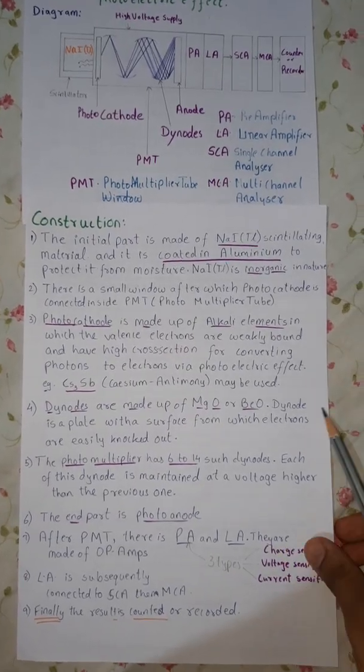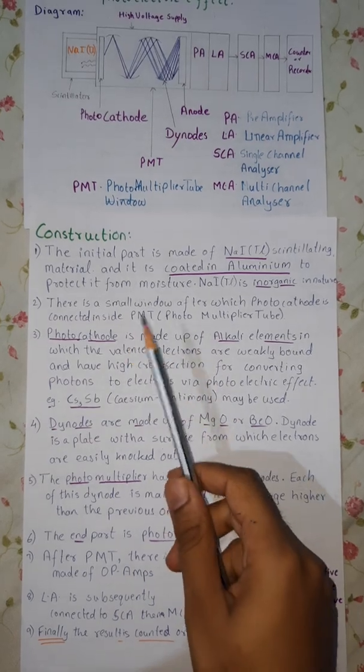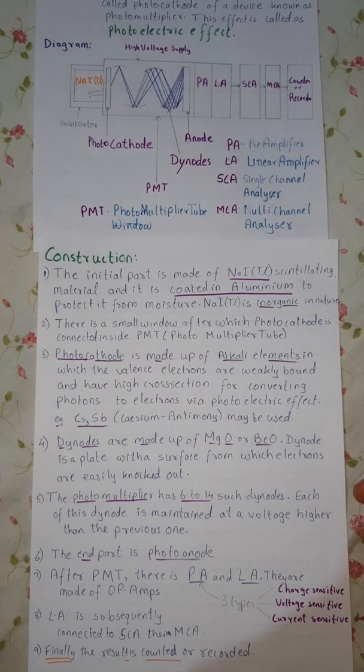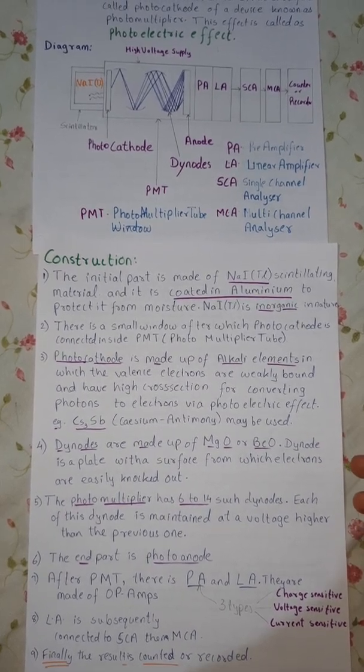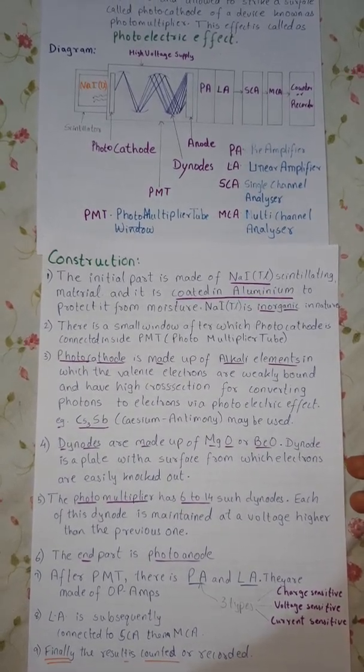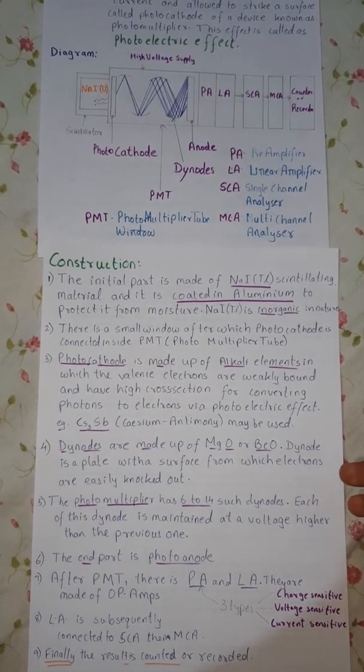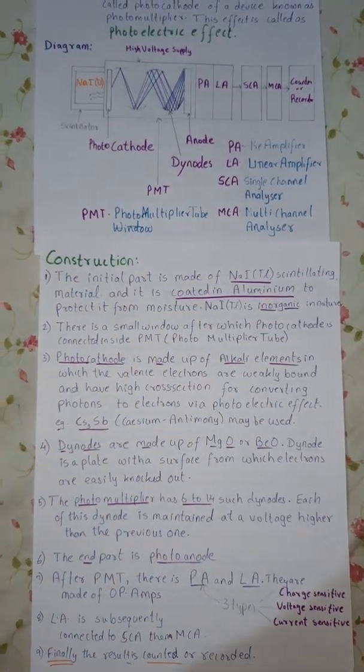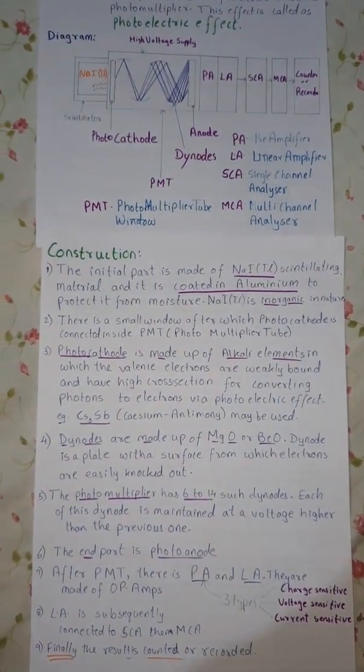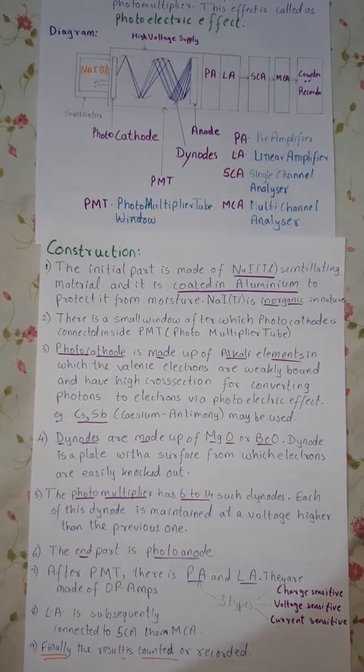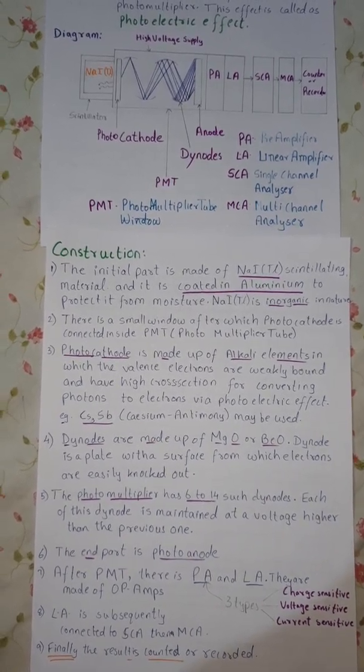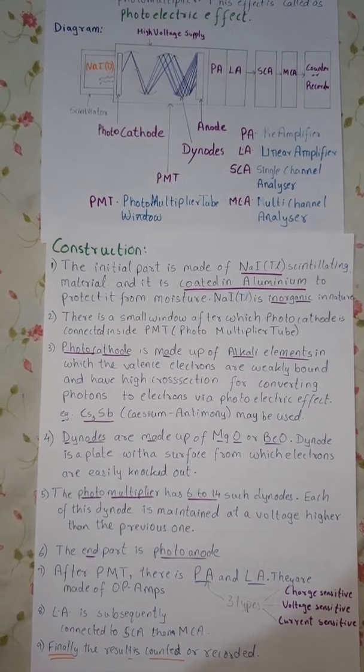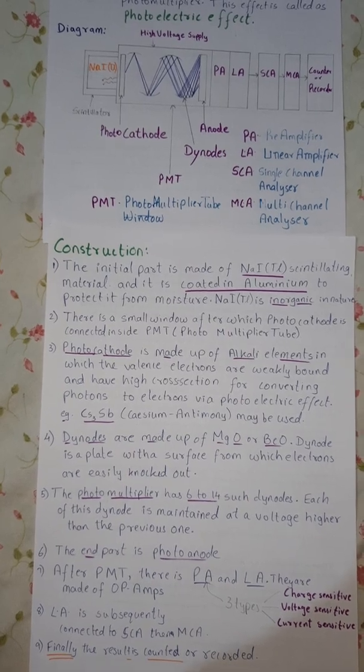Let us see the construction. The initial part of NaI(Tl) scintillating material is coated in aluminum to protect it from moisture. This is inorganic in nature. There is a small window present right over here. This window after which photocathode is connected inside PMT.